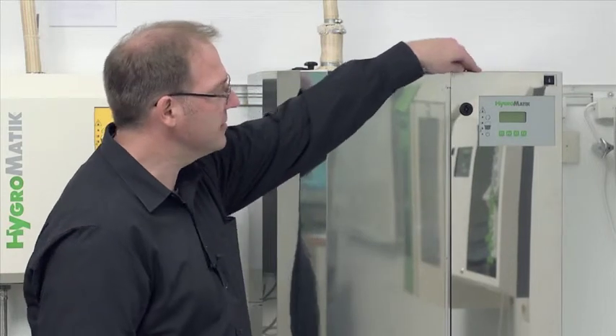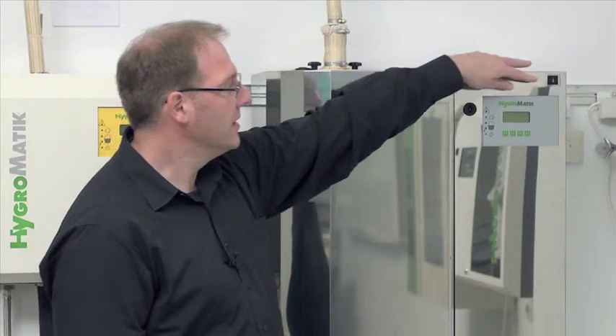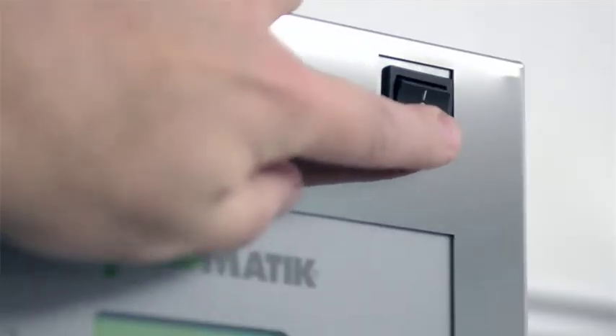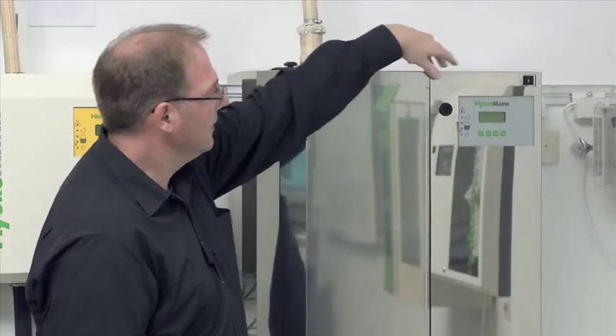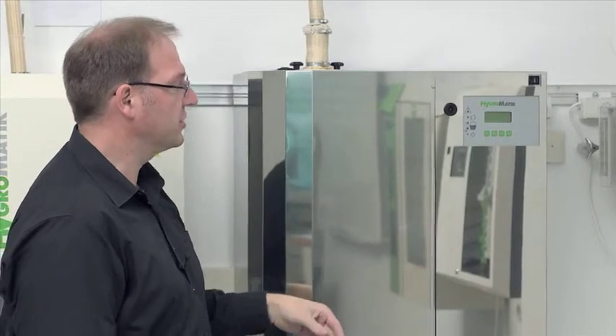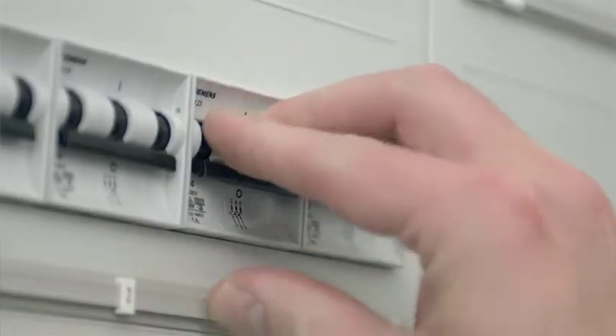Before I begin with the actual maintenance of the unit I first need to make sure that the water is drained from the steam cylinder. To do so I press and hold the control switch in position 2. After the water is now out of the steam cylinder I disconnect the unit from the power supply and secure it against being restarted.